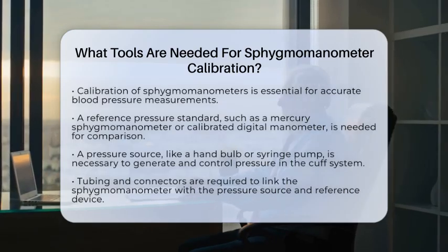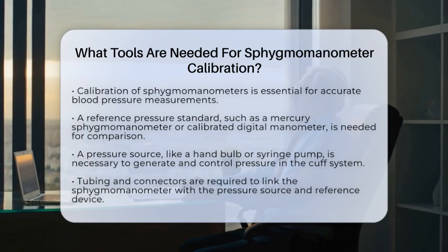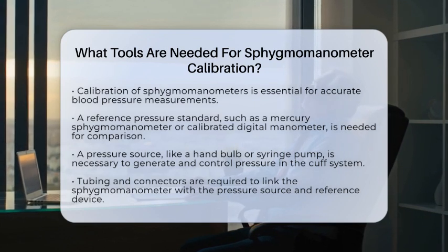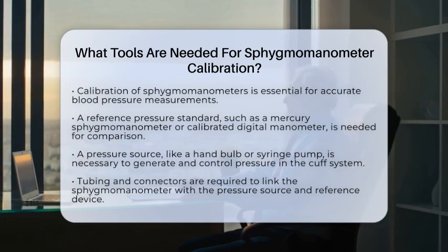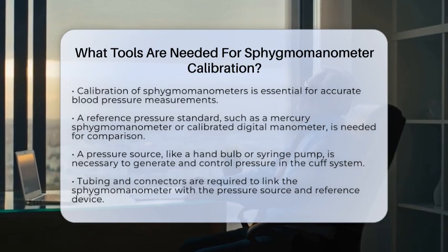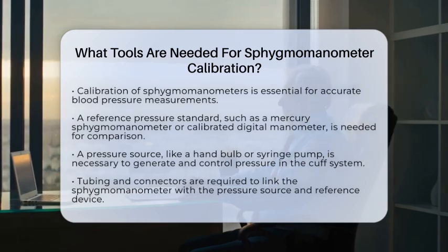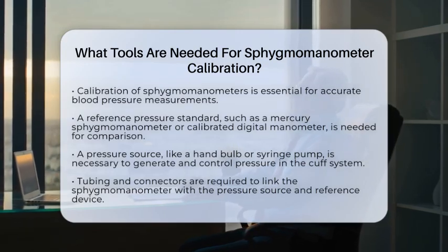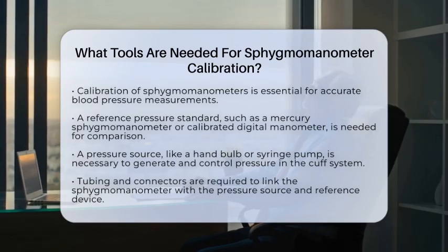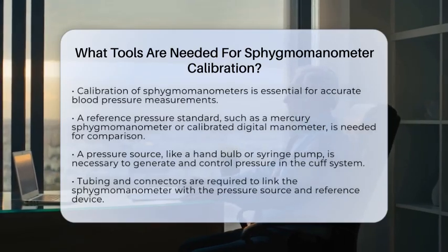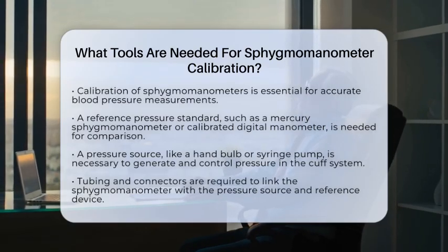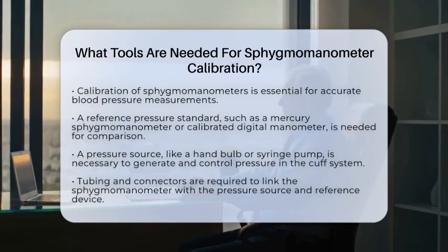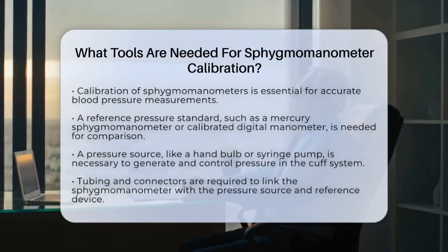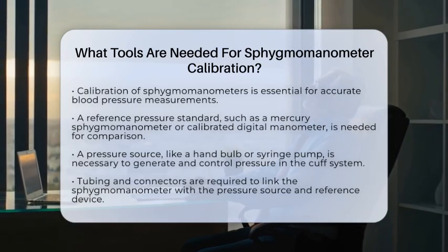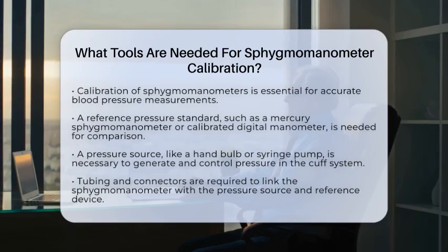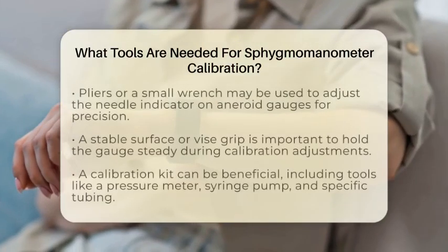To begin with, you will need a reference pressure standard. This can be a mercury sphygmomanometer or a calibrated digital manometer. This device acts as the benchmark to compare readings and verify accuracy. Next, a pressure source is essential. You can use a hand bulb or a syringe pump to generate and control pressure within the cuff system. This allows you to create the necessary conditions for testing the sphygmomanometer.